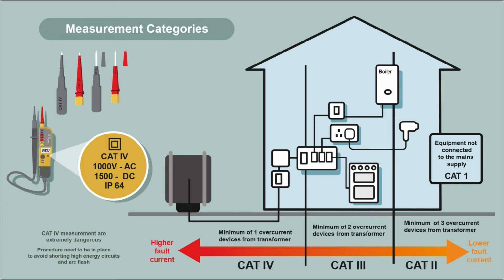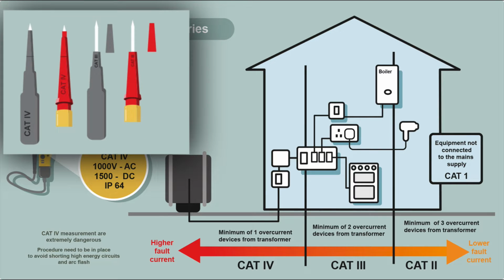In GS38, it tells us that the preferred length of the metal probe tip is 2 millimeters. Can go up to 4, but 2 is the preferred length. The reason is so you don't get any arcing between the two probes. And it is possible sometimes to take the plastic tip off the leads, you get more exposed metal. Sometimes you need to do that if you're going into a very small connector. But you'll notice on the leads that brings it down from a category 4 tester to a category 3 tester.